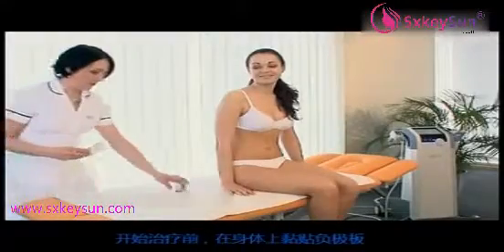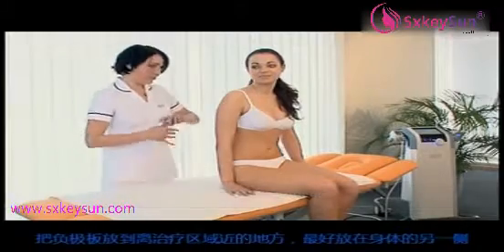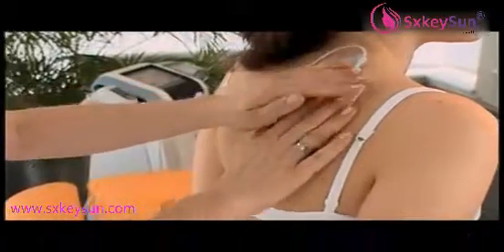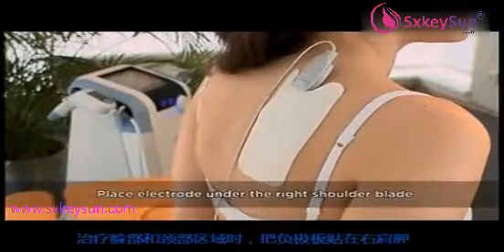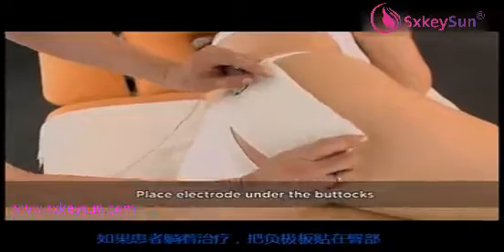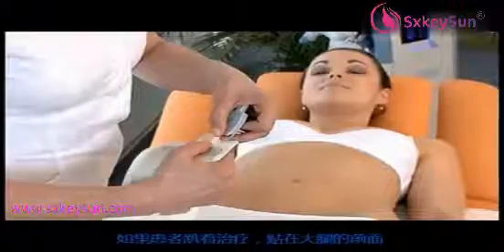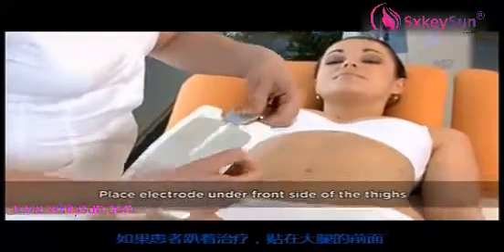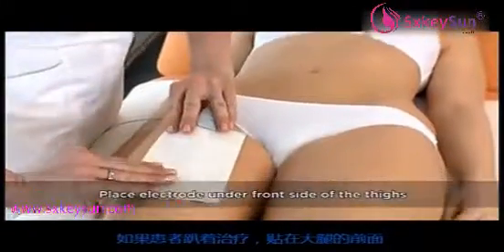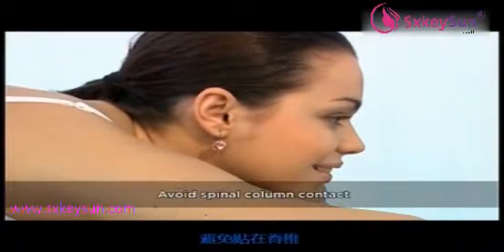To start the therapy, place the electrode on the body, close to the treated area, preferably on the opposite side of the body. For facial and neck applications, place the electrode under the right shoulder blade. For therapy where the patient lies on their back, place the electrode under the buttocks. For therapy where the patient lies on their abdomen, place the electrode under the front side of the thighs. Position the electrode on a soft tissue area rather than a bony one to ensure the best contact. Always avoid spinal column contact.